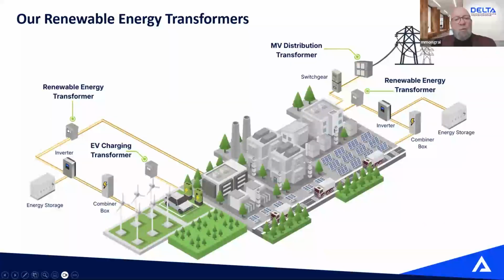So the transformer needs to be able to take energy either from the wind farm and the inverter all the way to the building, or sometimes, if the battery storage needs to be recharged, it can be the energy of the wind farm, or it could also be the energy from the building. So the transformer needs to be able to either get the power from the inverter and feed the building, or get the energy from the building and feed the inverter to recharge the batteries.